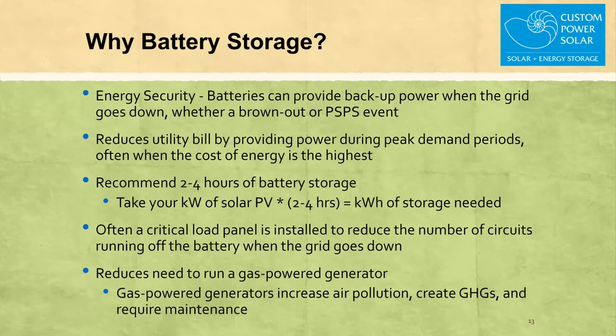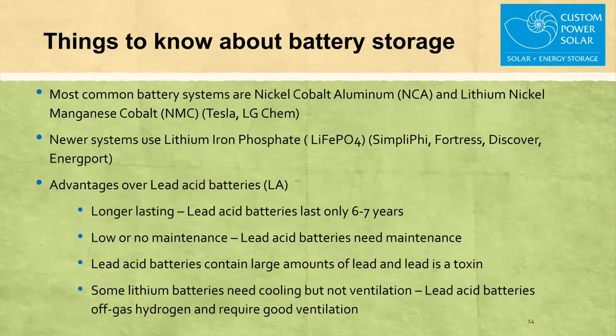So, things to know about batteries. The most common systems are called NCA and NMC, and those are Tesla and LG Chem. Some newer systems are the lithium iron phosphate. This is what we use. It's things like SimpliPhi, Fortress, Discover, Energport. There are others. Advantages: longer lasting than lead acid batteries, little to no maintenance. Lead acid batteries contain lead. Lead is a toxin. And some lithium batteries need cooling but not ventilation. Lead acid batteries will off-gas hydrogen and require good ventilation.